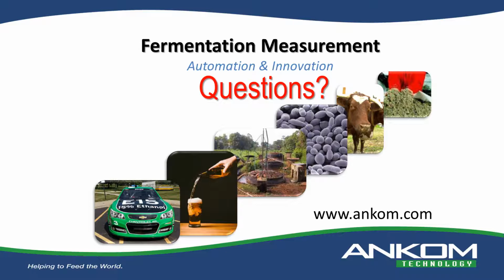Okay, next one. A real problem is battery life. I know we can use a 2-lead system and a plug-in, but this is a move away from a wireless system. Any good ideas? Your point is valid. And it's interesting because we have some people that are actually doing month-long studies. And what they're doing is they are changing the batteries during an operation. And the beauty of that, or the way the software is designed, is if you have, let's say, 50 modules running, and you're doing long studies, and you're noticing the batteries are going to yellow, you want to change them. Even if data is being requested at the time you're making the change of the battery, the system holds it.